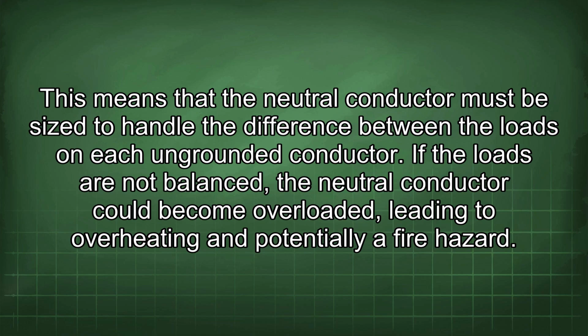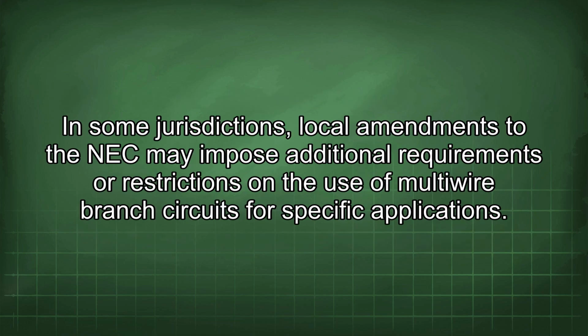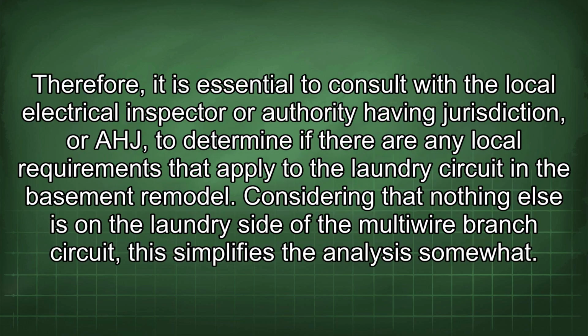In some jurisdictions, local amendments to the NEC may impose additional requirements or restrictions on the use of multiwire branch circuits for specific applications. Therefore, it is essential to consult with the local electrical inspector or authority having jurisdiction, or AHJ, to determine if there are any local requirements that apply to the laundry circuit in the basement remodel. Considering that nothing else is on the laundry side of the multiwire branch circuit, this simplifies the analysis somewhat.